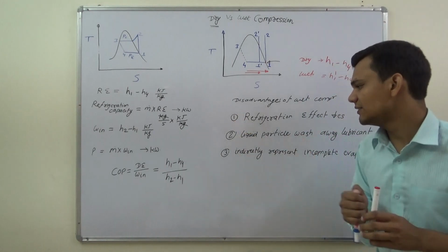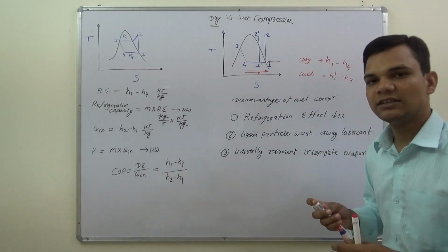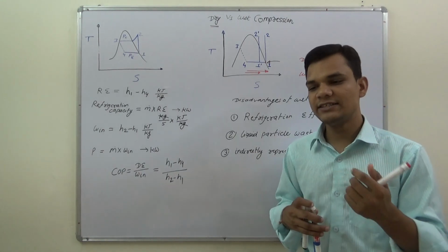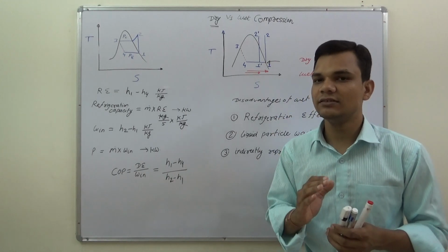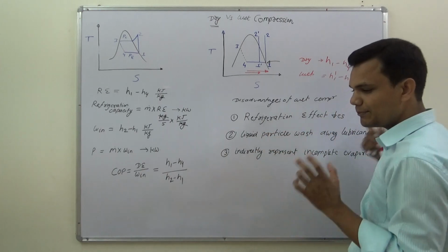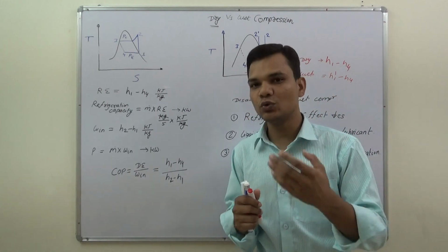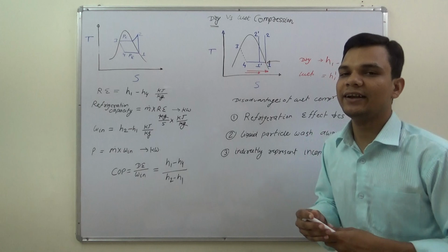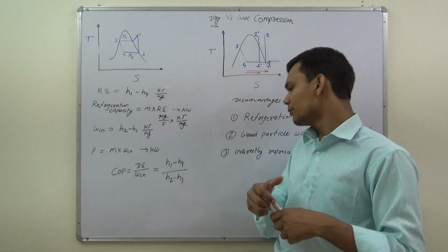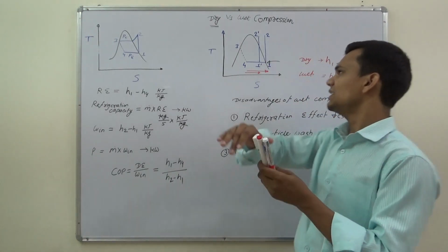So the first disadvantage is that the refrigeration effect gets decreased. The second disadvantage is that the liquid particles present in the mixture of liquid and vapor wash away the liquid lubricant, so it increases the chances of wear and tear, and also increases the chances of damage to the compressor body and its valves. And the third disadvantage is that it indirectly shows incomplete evaporation.